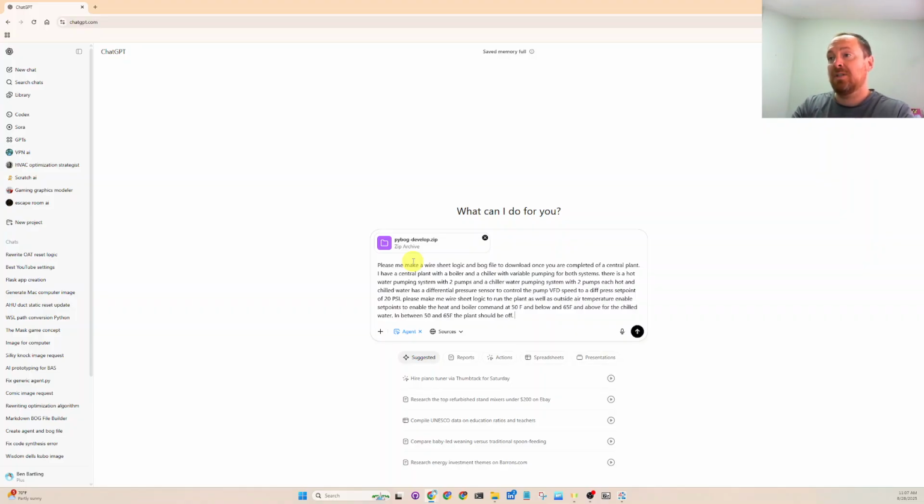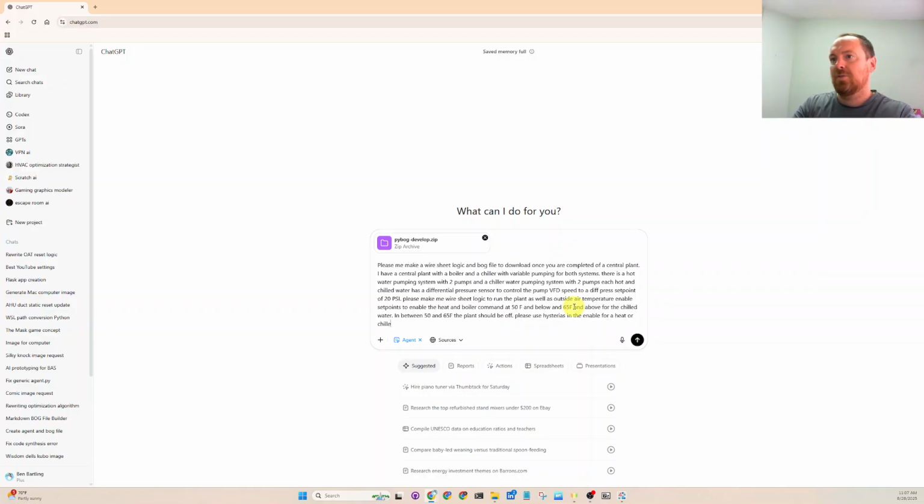And I'm going to also say something. Please use hysteresis in the enable for a heat or chilled water system. Please provide an output for a boiler or a chiller as well. So I'm just making something up, thinking and typing.